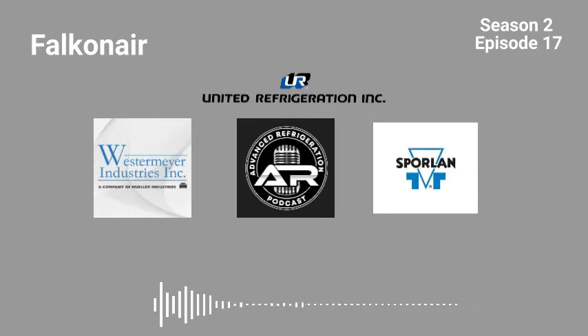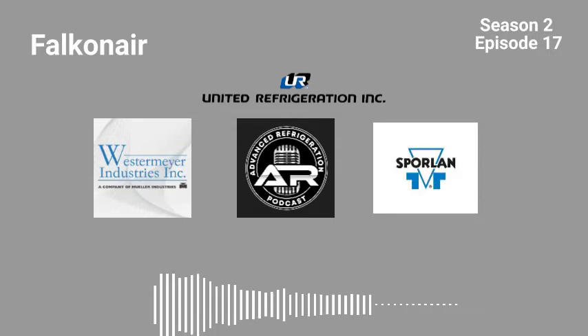An oil return sequence program is normal on every DC inverter system out there. If you buy a brand new DC inverter system and put a monitor on, you're going to see at one point that it does an oil return sequence. An oil return sequence is purely running the compressor at full speed to bring back any oil that went out of your compressor and is flowing into the system. Our smart compressor control has that included also. It's part of the program.